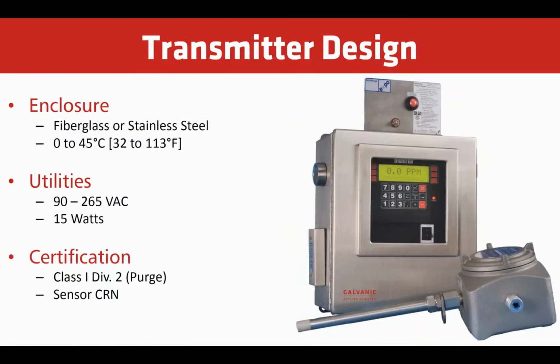Here we're looking at some different transmitter designs. Standard is a fiberglass NEMA 4X box, and that's for general purpose for the transmitter. Or we can offer, as we see in the photo here, the NEMA 4X stainless steel box with Z-Purge for Class 1 Div 2 installations. The sensor always, no matter what, is Class 1 Div 2 rated. What's required to power this unit up is the universal power, 90 to 265 volts AC, 50-60 hertz. It draws approximately 15 watts when in use. And again, we have the unit certified Class 1 Div 2 with instrument air purge or a Z-Purge.